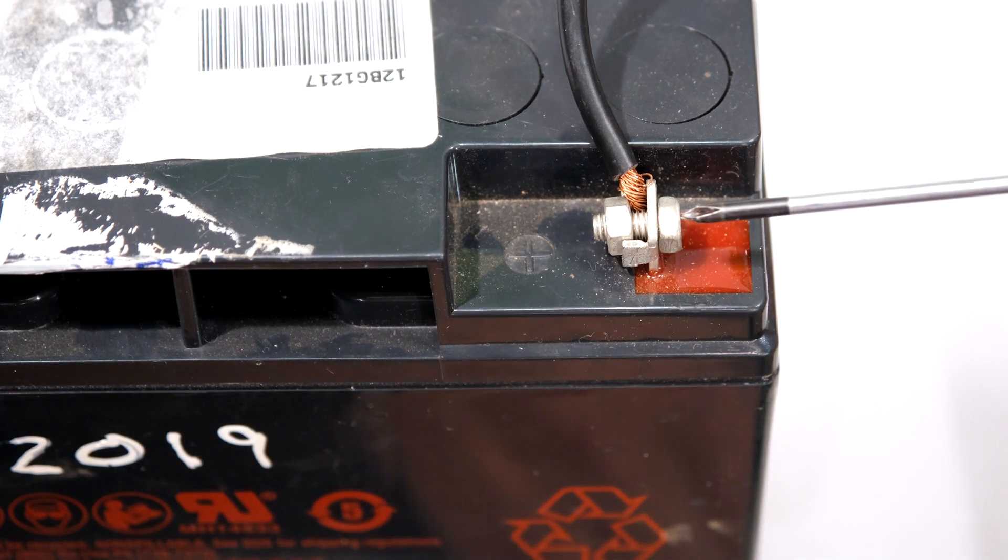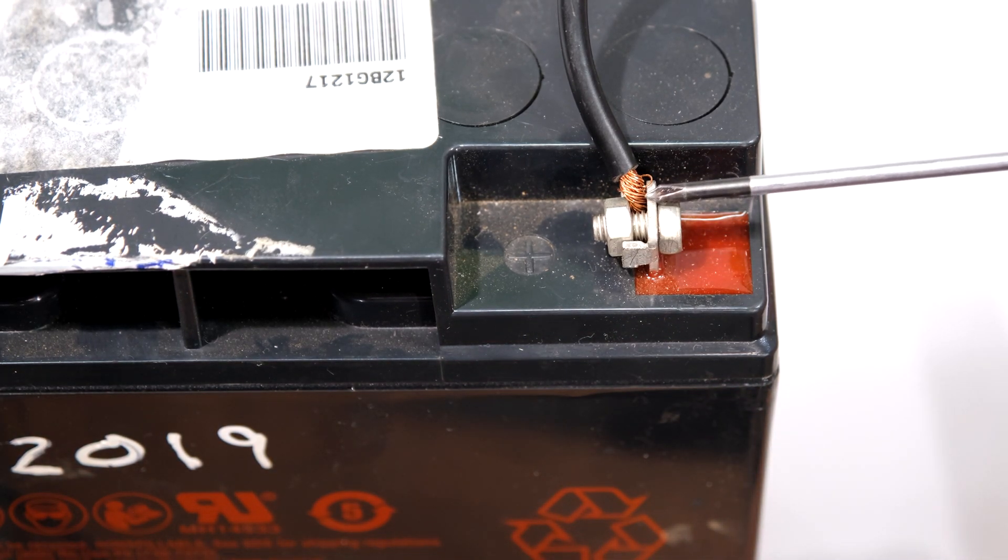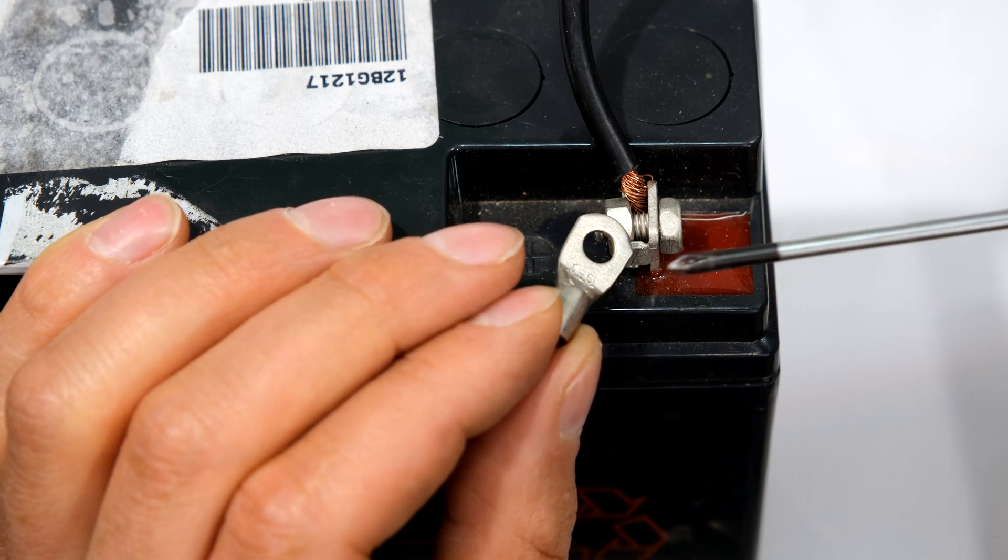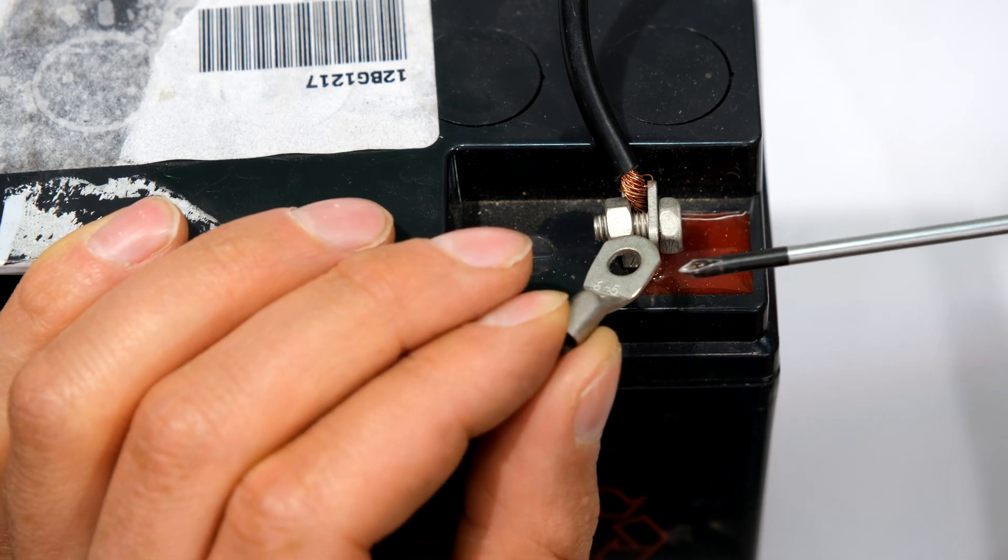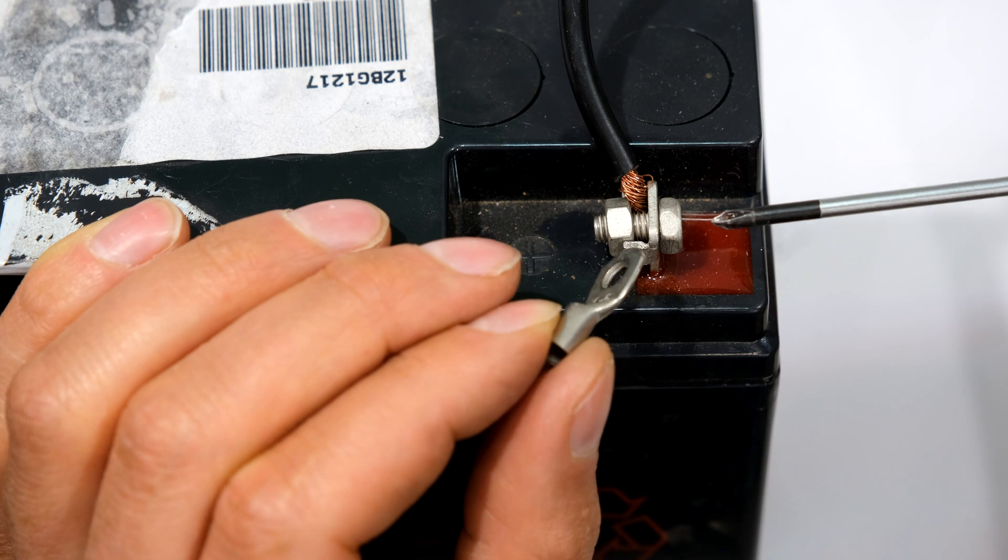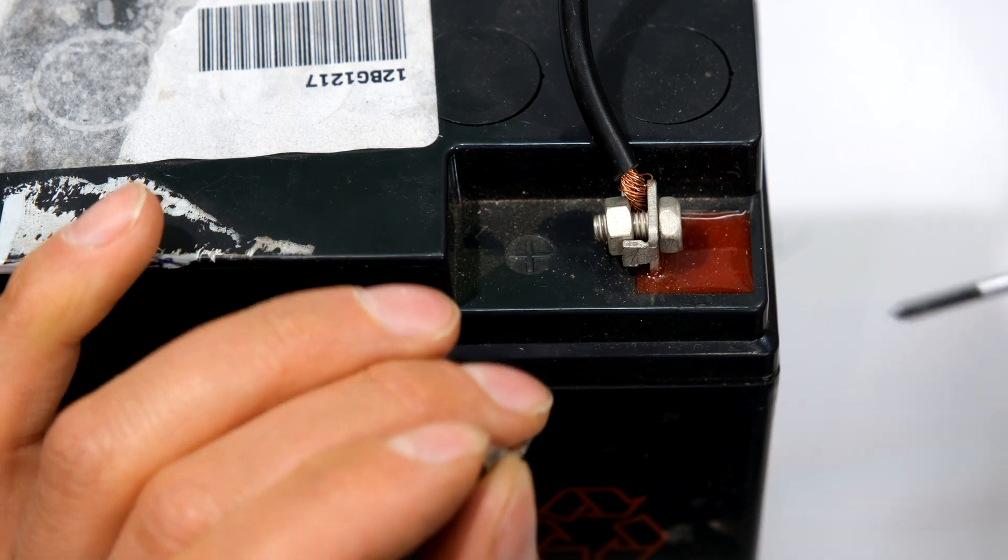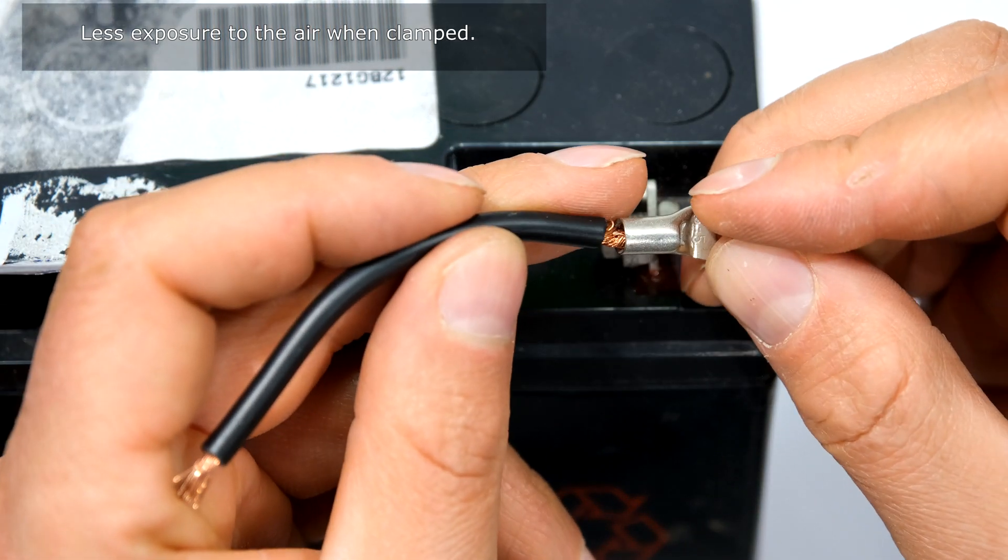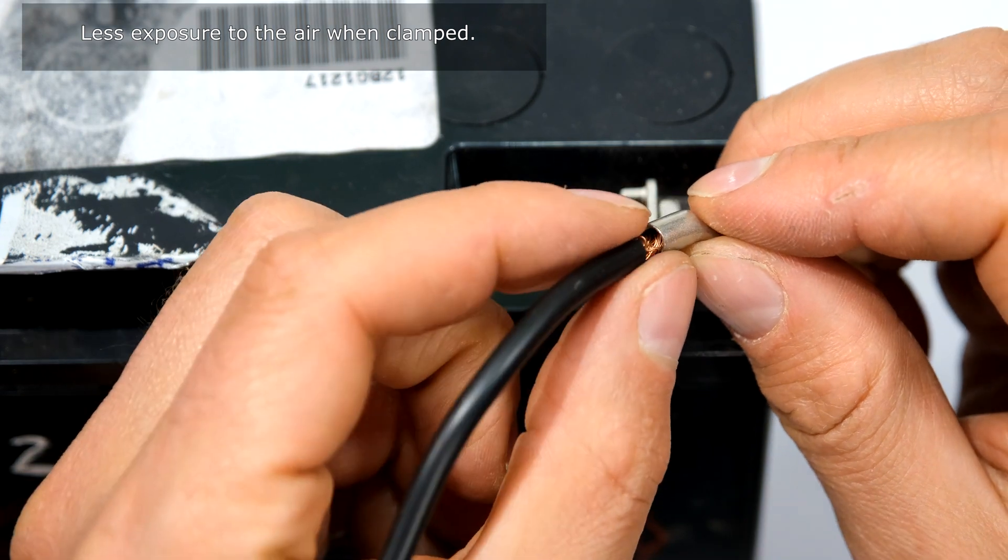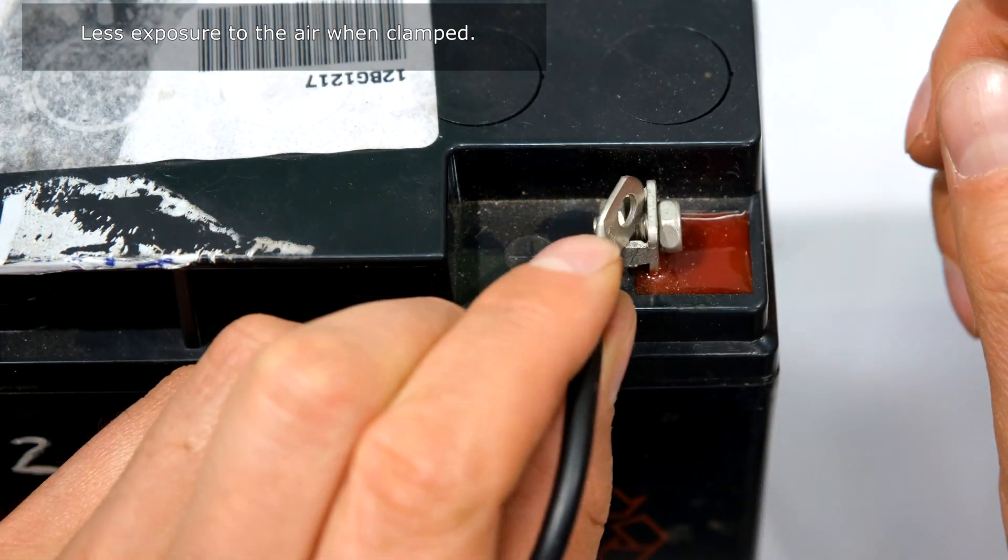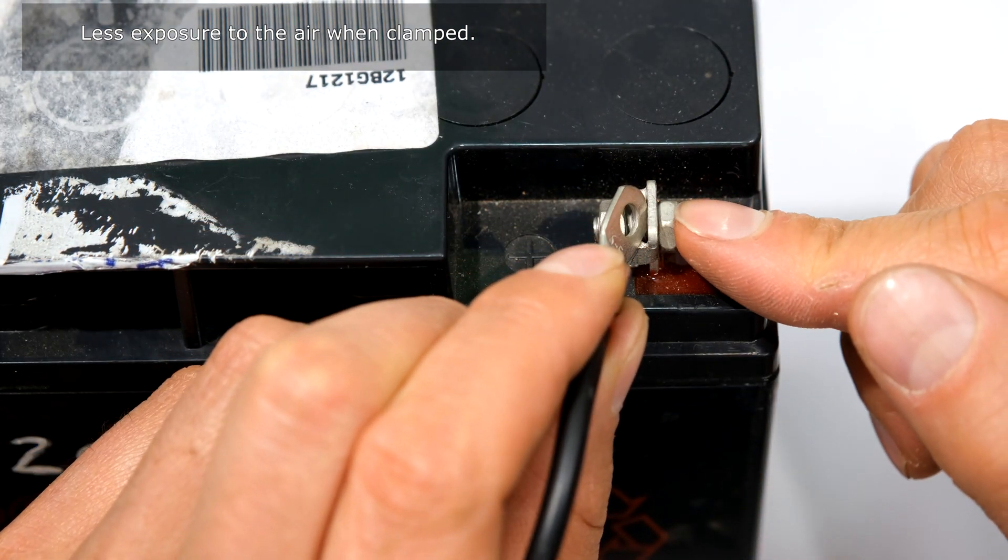This is an example of where people have not considered the contact resistance. By using a lug like this, you can see the surface area is bigger, and a bigger surface area reduces the contact resistance. So what should have happened is this should have been inside here, this could have been soldered, and a lug could have been used for this terminal.